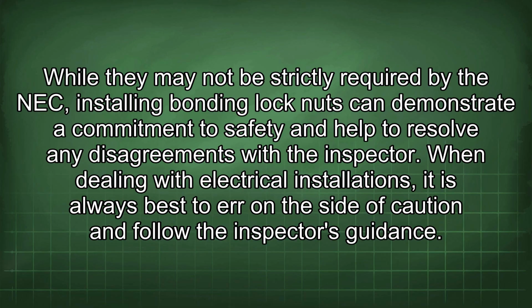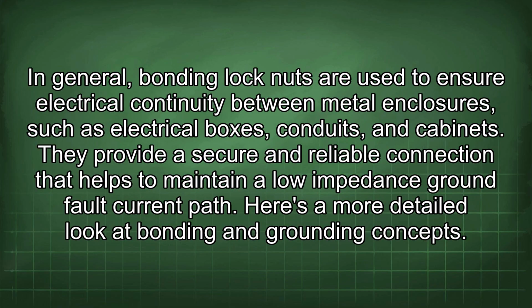When dealing with electrical installations, it is always best to err on the side of caution and follow the inspector's guidance. In general, bonding lock nuts are used to ensure electrical continuity between metal enclosures, such as electrical boxes, conduits, and cabinets. They provide a secure and reliable connection that helps to maintain a low impedance ground fault current path. Here's a more detailed look at bonding and grounding concepts.